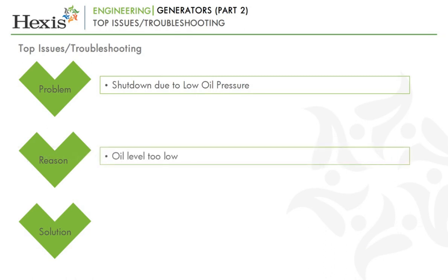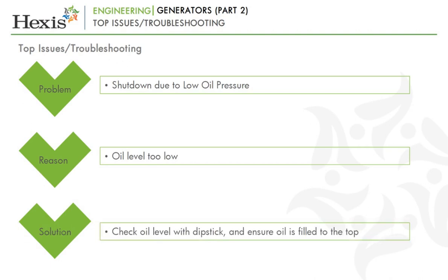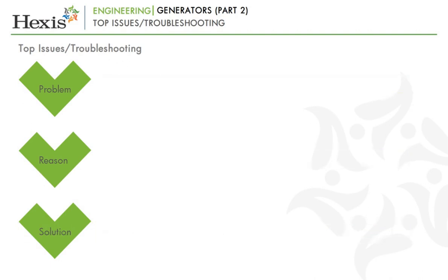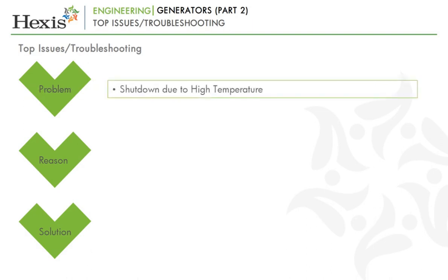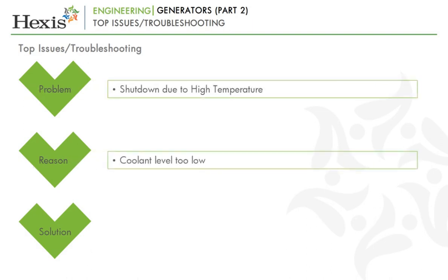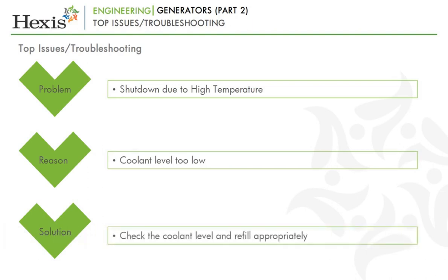Problem: shut down due to low oil pressure. Reason: the reason could be that the oil level is too low. Solution: check with dipstick and ensure oil top off. Problem: shut down due to high temperature. Reason: coolant level is too low. Solution: coolant levels should be checked and appropriately refilled.